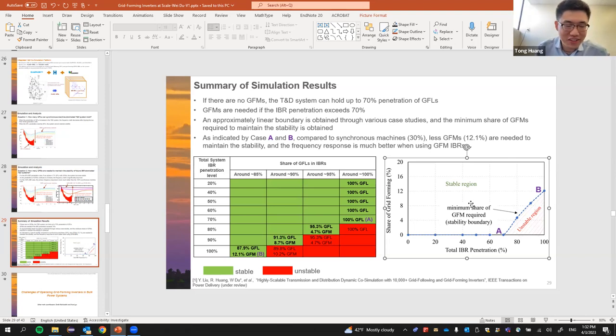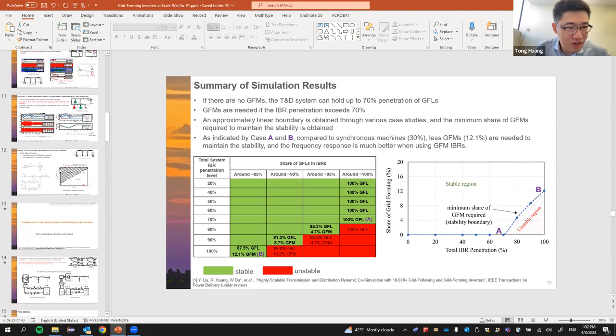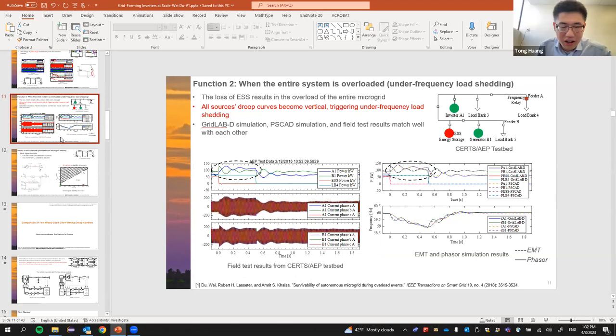My third question is about the single loop control. One slide talks about under frequency load shedding. Yes, this one. For this slide, I have a question. Here, you address this overload issue by lowering the frequency and triggering the under frequency relay to shed the load. Would it be possible to do it the following way? Suppose we have overload, we try to redispatch the generation produced by each IBR to balance the actual load. Would that be possible? I think that depends on the scenario. For this scenario, no sources have available power to supply the additional load. In this microgrid, the total load is larger than the source, so you have to trip some load. Yeah, that makes sense.